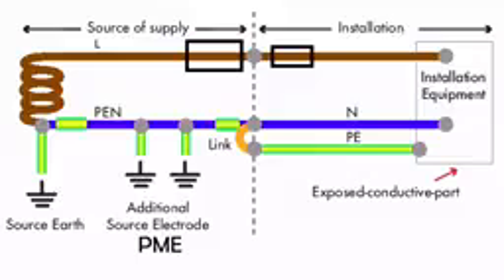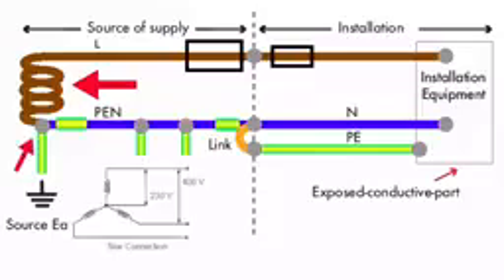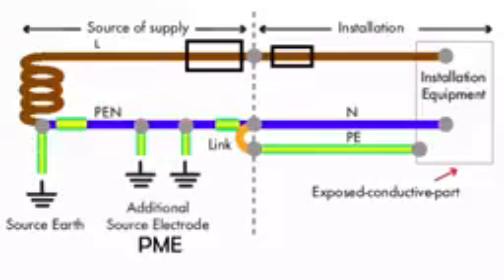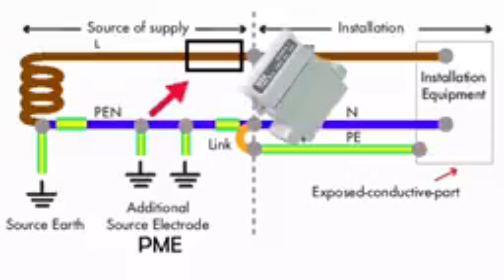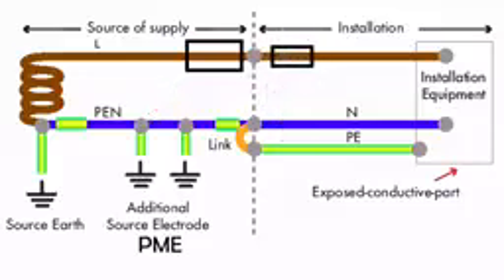This drawing also only shows one of the star connected windings on the supply authority's side as well as the centre tap point to earth. The supply authorities will provide the metering equipment and cutout fuse rated either 100, 80 or 60 amps for a single phase domestic dwelling.